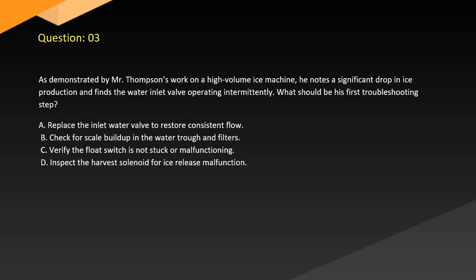Question 3. As demonstrated by Mr. Thompson's work on a high-volume ice machine, he notes a significant drop in ice production and finds the water inlet valve operating intermittently. What should be his first troubleshooting step? A. Replace the inlet water valve to restore consistent flow. B. Check for scale buildup in the water trough and filters. C. Verify the float switch is not stuck or malfunctioning. D. Inspect the harvest solenoid for ice release malfunction.